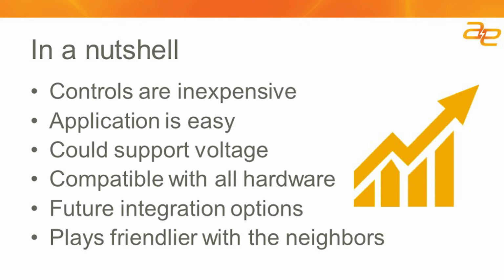The RTAC talks Modbus, it talks DNP3, it talks its own protocol, it talks the GOOSE protocol. So any of the standard protocols for devices that exist in the solar power plant, the RTAC is capable of communicating with, so it's compatible with all the types of hardware that we run into. And it gives you some integration options down the line, like I mentioned, automatic generation control, power factor control, and has some capabilities built in to interface with other external systems. And lastly, having a system that responds a little more slowly and is less disruptive to the grid just allows the site to play friendlier with the neighbors.